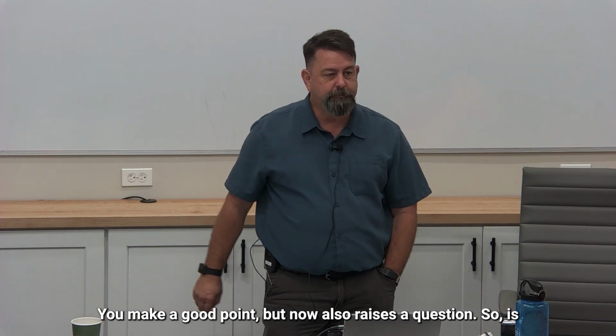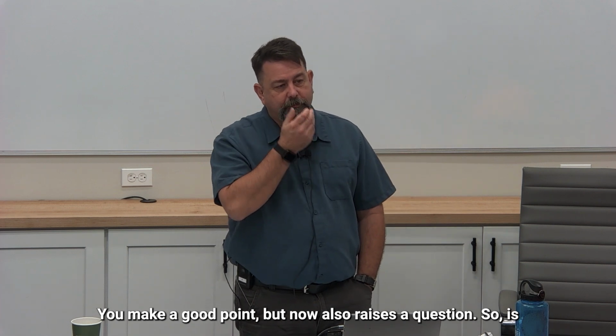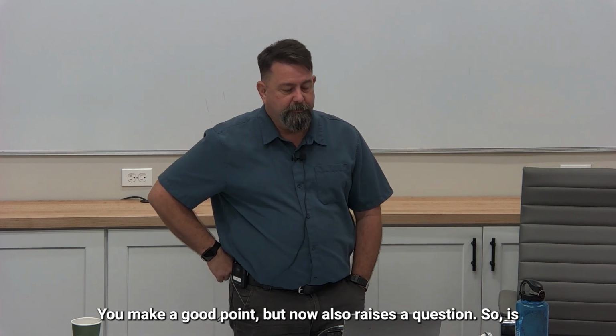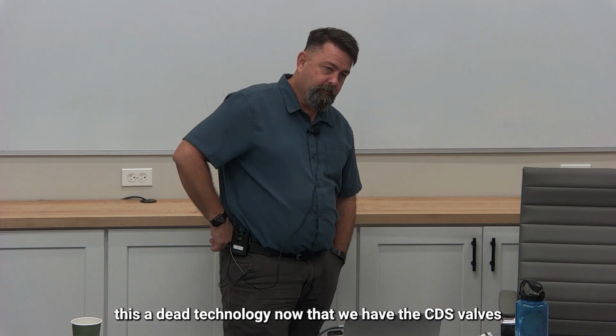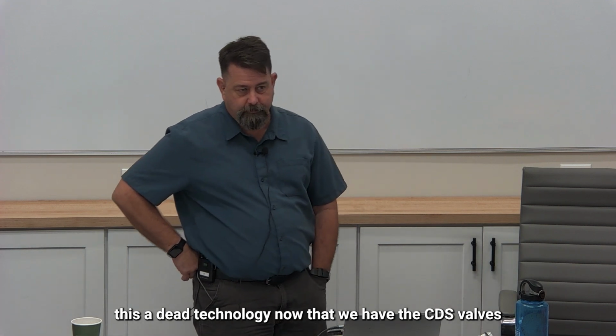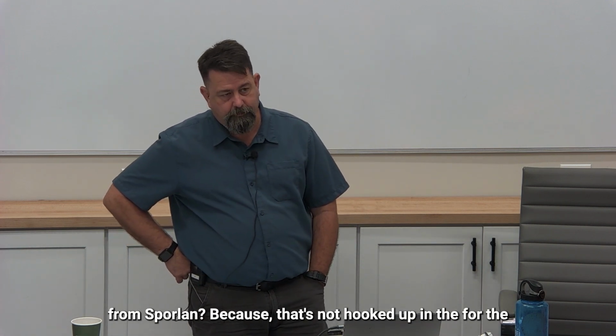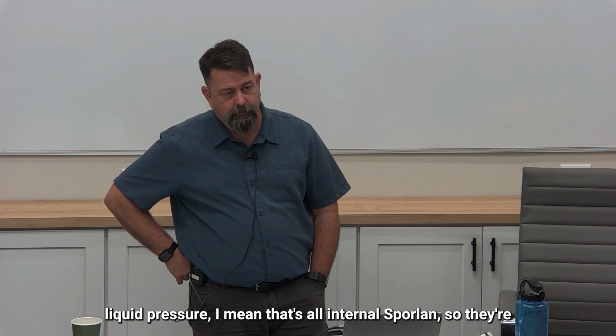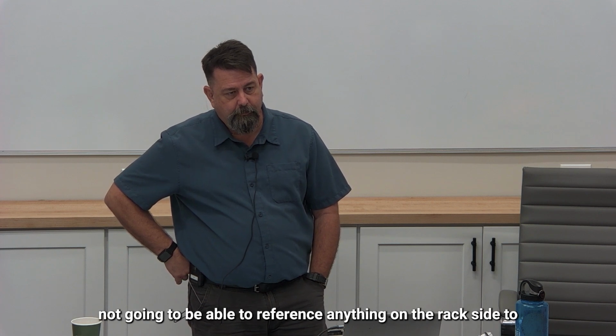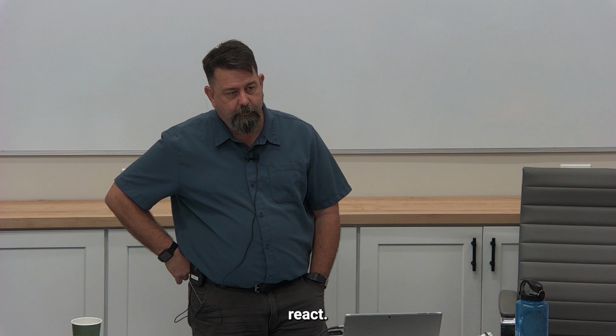Yes, sir, you make a good point, but now it also raises a question: is this a dead technology now that we have the CDS valves from Sporlan? Because that's not hooked up in it, for the liquid pressure, I mean, that's all internal to Sporlan, so they're not gonna be able to reference anything on the rack side to react. All right, so yes and no, right? The way that we're typically seeing it used is no, it can't.